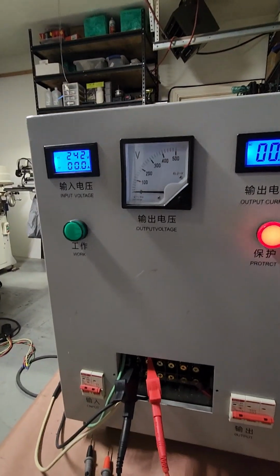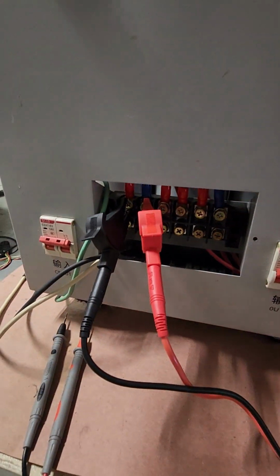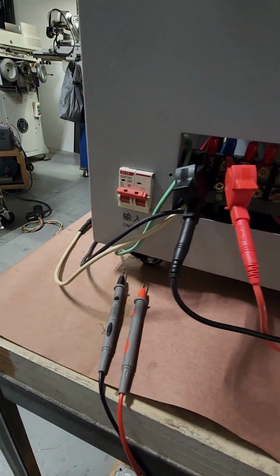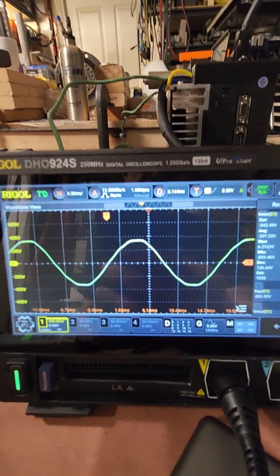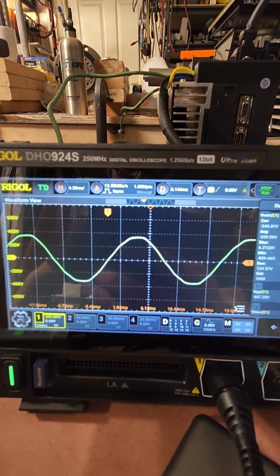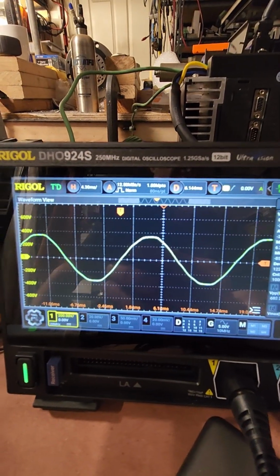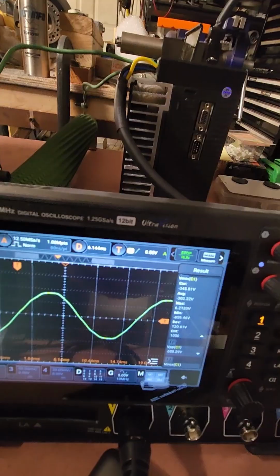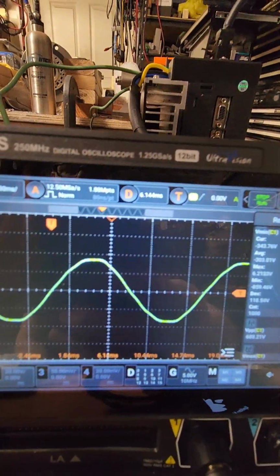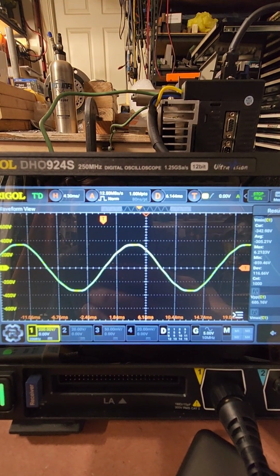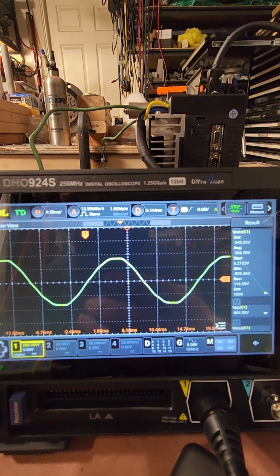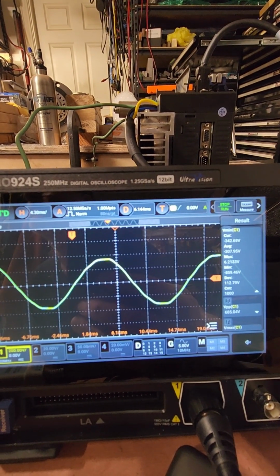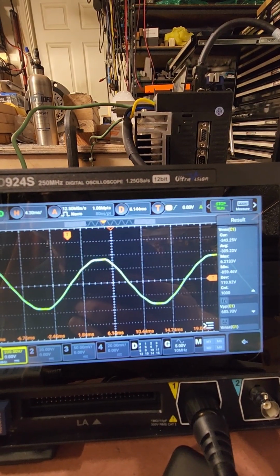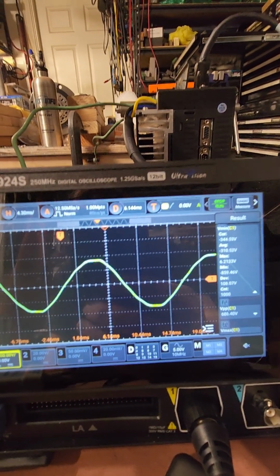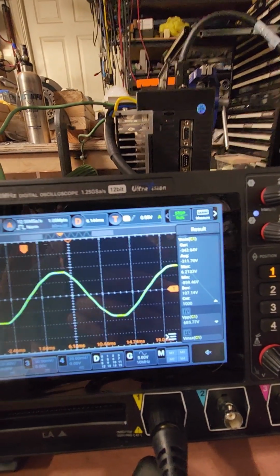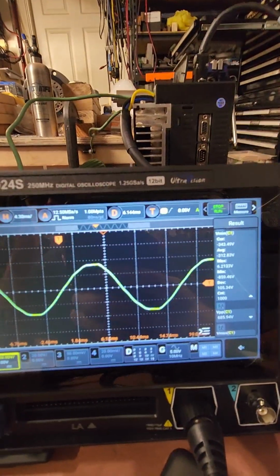So I have this powered off. You see, 0 voltage here, and I have the probe on the 240 volts main, and we are looking at that wave. That's how it looks like. And I'm gonna power this converter to see if we can see any switching noise showing up on that wave. So here we go. We are at 200 volts, 300, 360. So I'm not seeing anything. So maybe 8 kilohertz is fine.